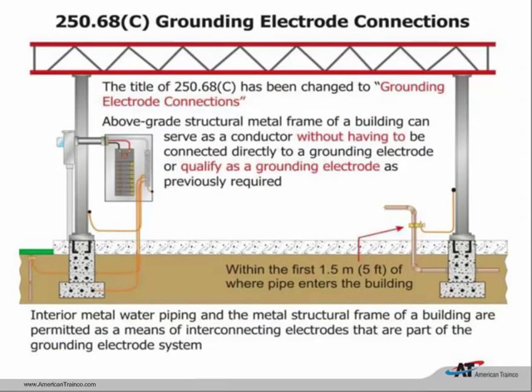In Article 250, grounding and bonding, a slight change was made to grounding electrode connections. If the water pipe enters the building far away from the service entrance, the code committee has now allowed the metal steel frame of the building to be used as a bonding conductor—as long as there is a metal-to-metal connection all the way back to the service. As long as it's metal-to-metal, we can use the steel frame to connect the water pipe grounding electrode back to the service without running a wire the entire length of the building.